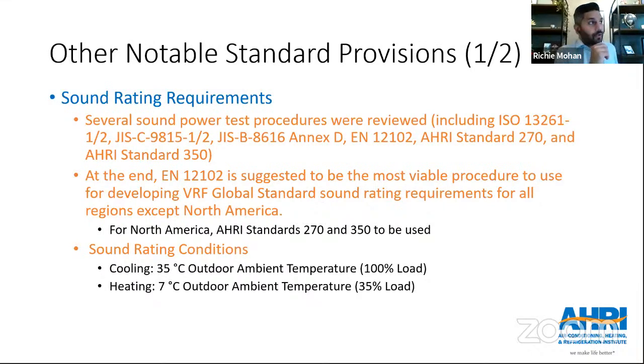Some other notable provisions are also being added to the standard or test procedure. One thing I would mention is that sound is very important. As population density grows in major metropolitan cities, noise pollution and noise emittance has to be addressed, which is why HVAC systems have to have sound ratings and a standardized method for measuring sound.